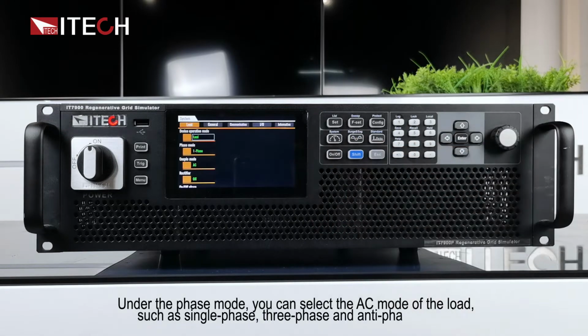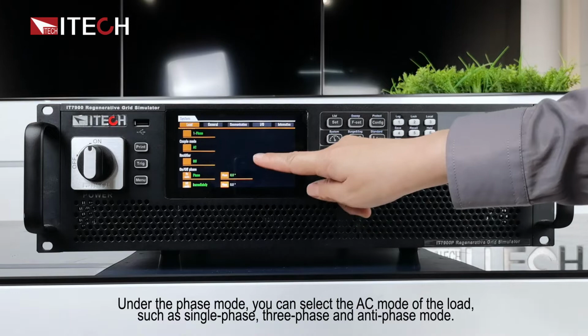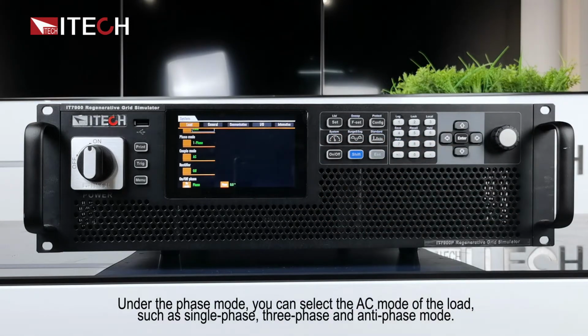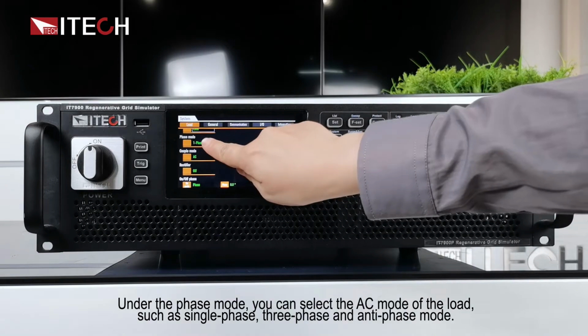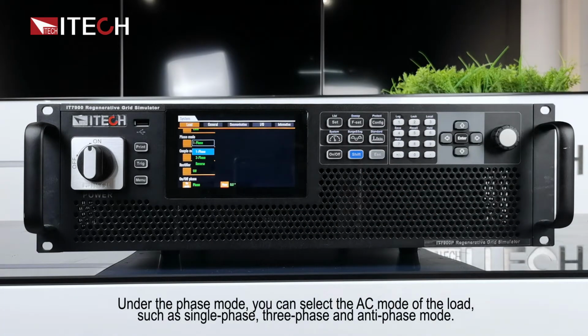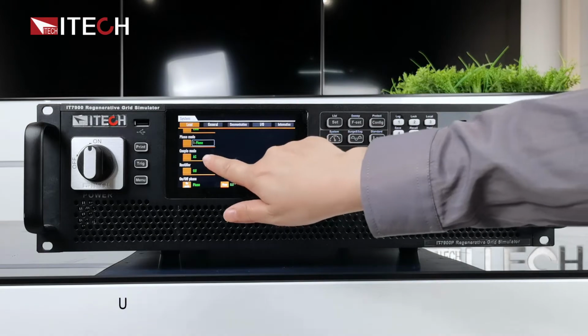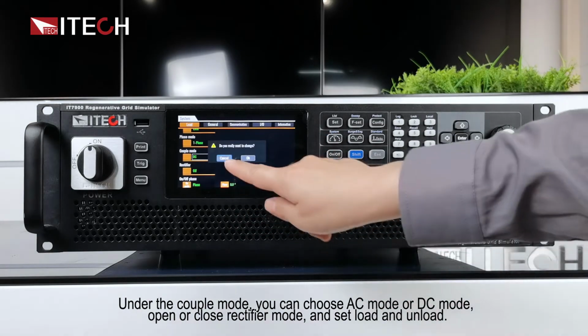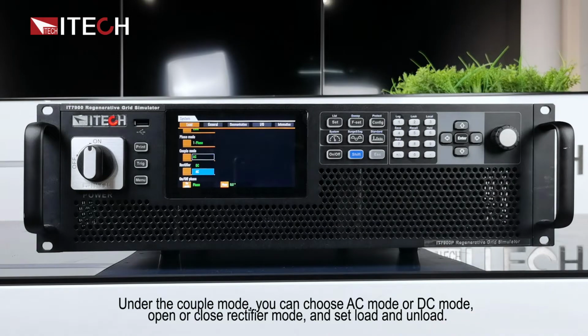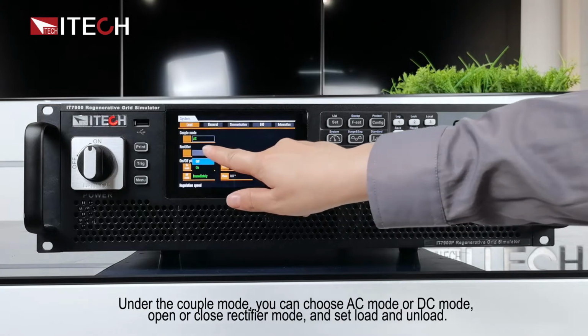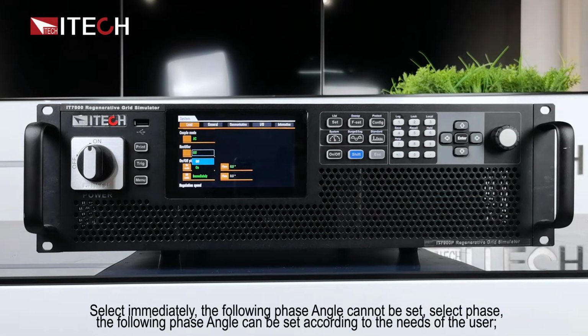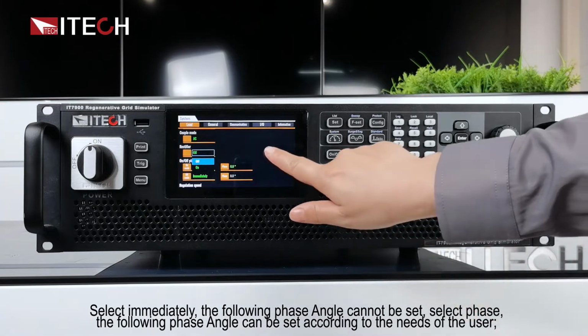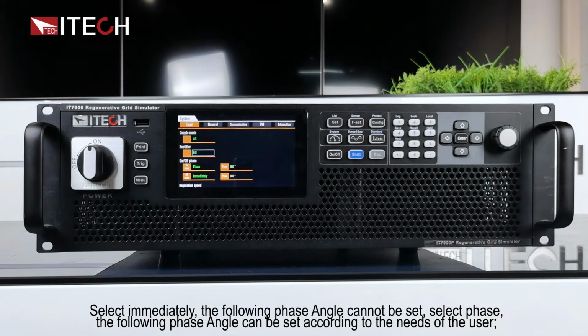Under the phase mode, you can select the AC mode of the load, such as single phase, three-phase and anti-phase mode. Under the couple mode, you can choose AC mode or DC mode, open or close rectifier mode, and set load and unload. Select immediately, the following phase angle cannot be set. Select phase, the following phase angle can be set according to the needs of the user.